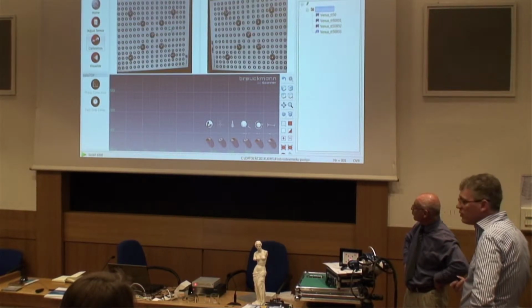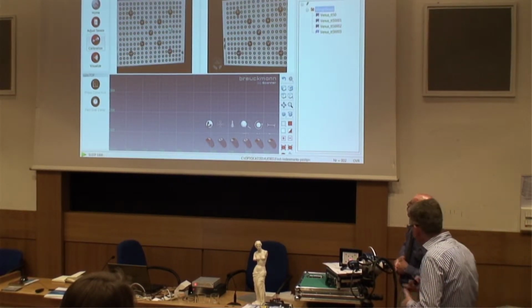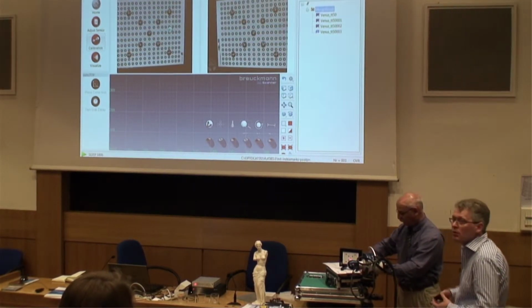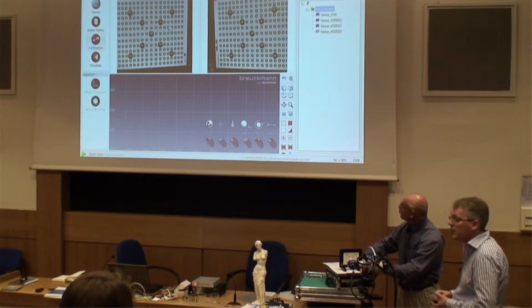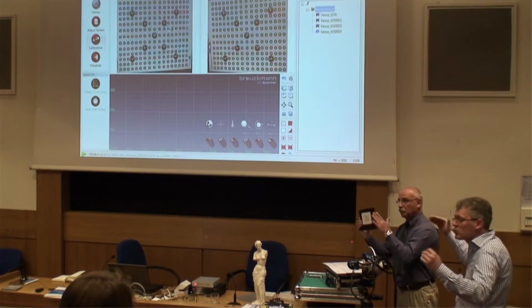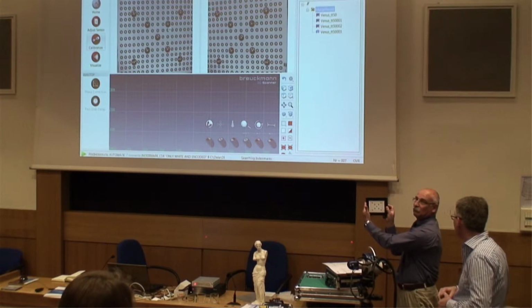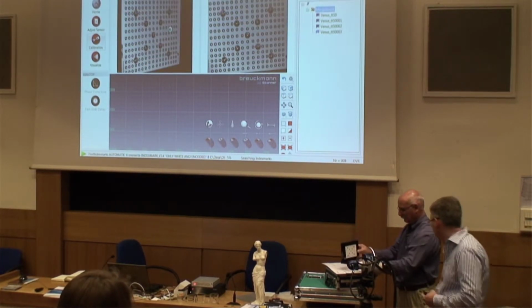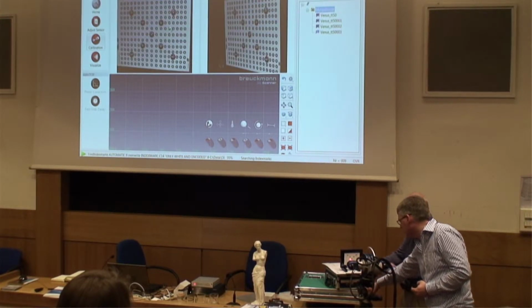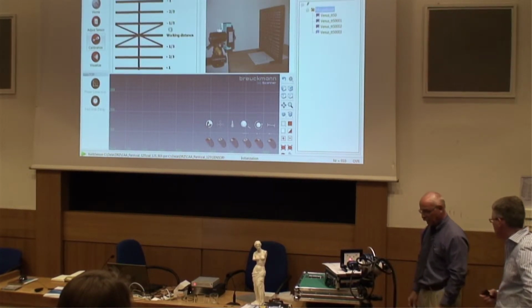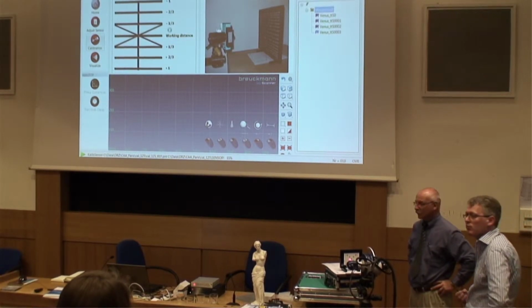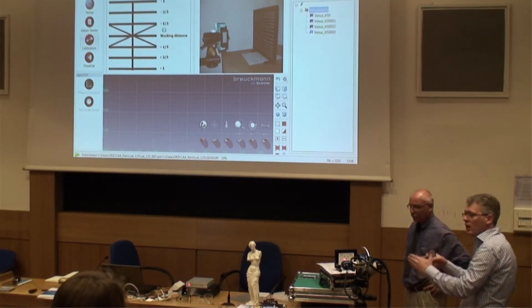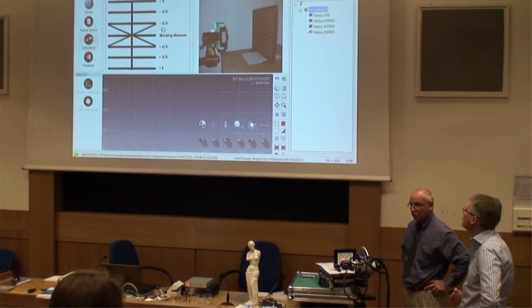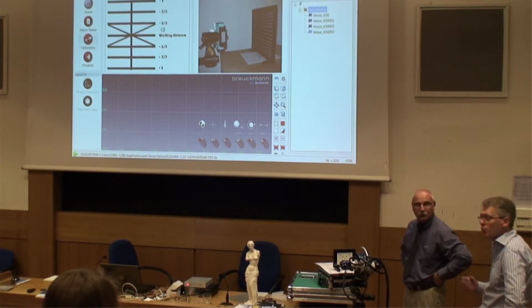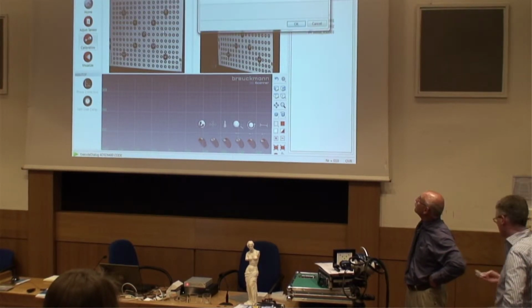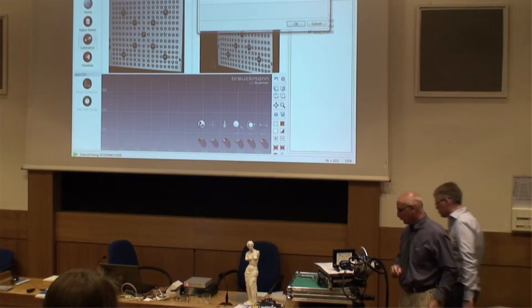And for each field of view, you not only need lenses, but you will need a proper calibration board. So this one has two sides, a very small one and a larger one. If you have a very large coverage, then you need a larger calibration board. So here, this is two sizes larger, that's an L plate. Larger for larger fields of view, and then for the very large ones, you have to move the scanner to cover all the areas because you don't want to have a huge suitcase of 2 by 2 meters maybe. So then you move the scanner to extended positions to do the calibration. So calibration is valid.